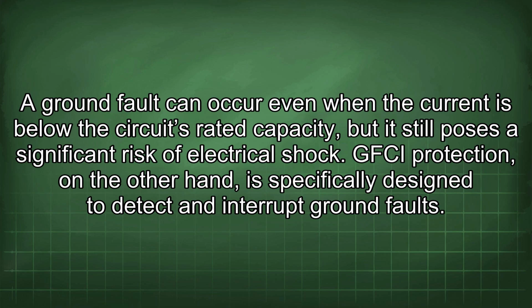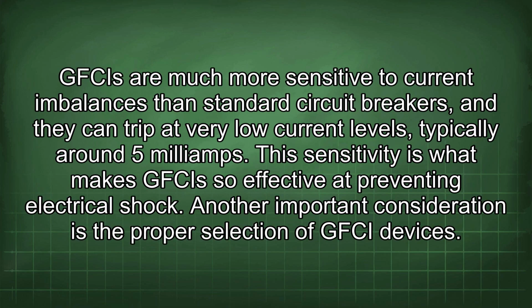GFCI protection, on the other hand, is specifically designed to detect and interrupt ground faults. GFCIs are much more sensitive to current imbalances than standard circuit breakers, and they can trip at very low current levels, typically around 5 mA.